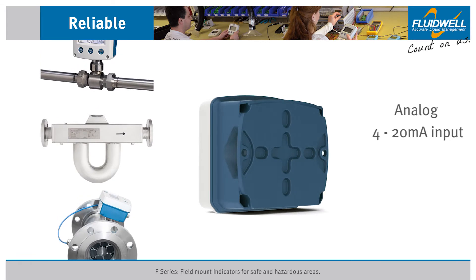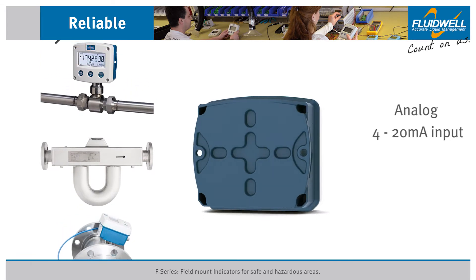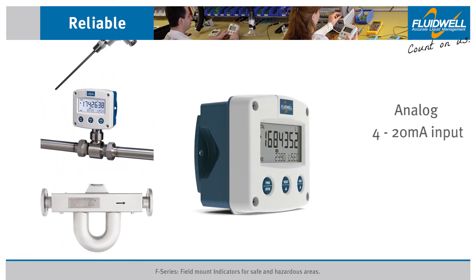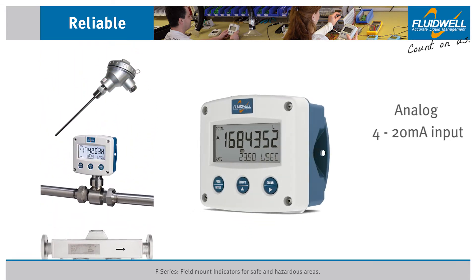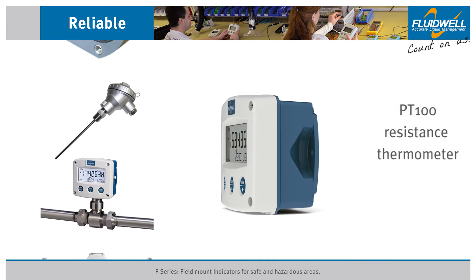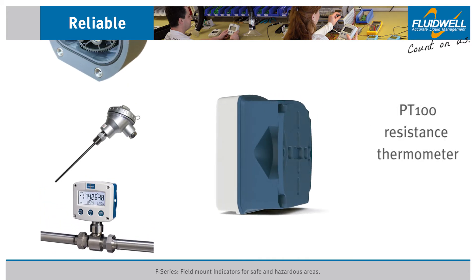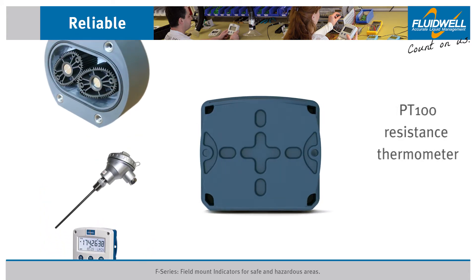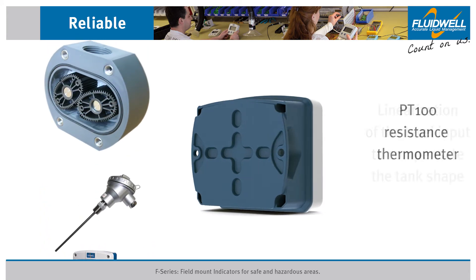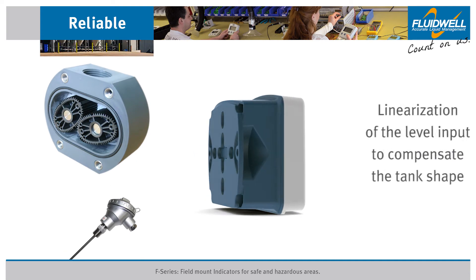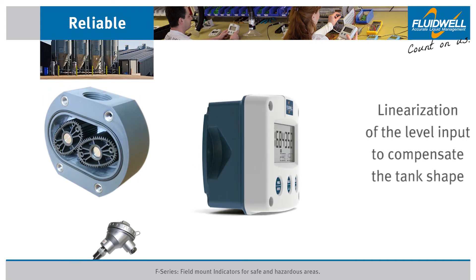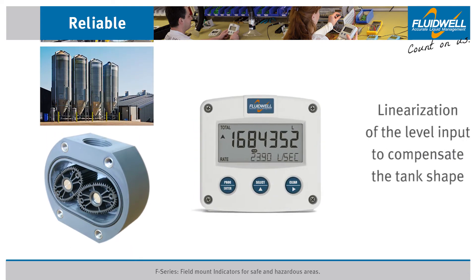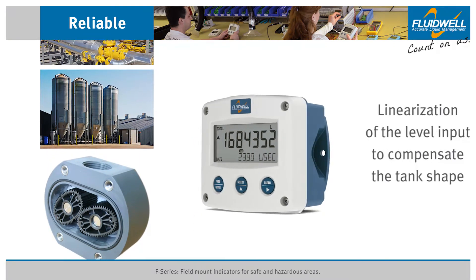Analog 4 to 20 milliamps inputs are available for level, pressure and temperature measurements. A PT-100 resistance thermometer input is also supported. Linearization of the input signal is available for level applications to compensate the tank shape.